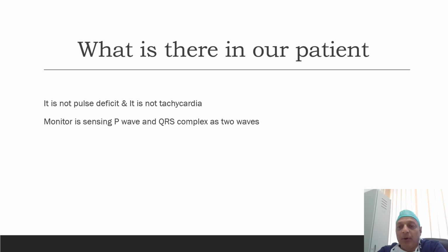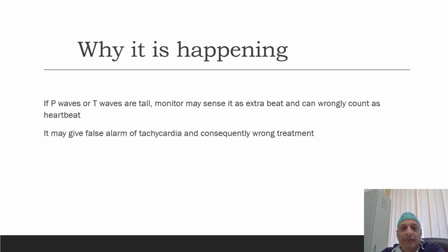misrecognizing the information from the cardiac monitor. If P waves or T waves are tall, the monitor may sense them as an extra beat and can wrongly count them as a heartbeat. It may give a false alarm of tachycardia or ventricular tachycardia and consequently wrong treatment of the patient.